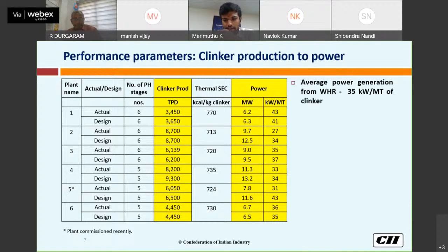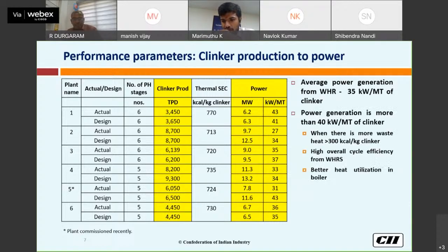Based on the table, the average power generation from WHR in India is around 35 kilowatt per metric ton of clinker, and one of the units generates more than 40 kilowatt per metric ton, where there is more waste heat, greater than 300 kilocalorie per kg. As I said, around 42% of heat we are wasting into the ambient. In this there are some avoidable losses. If the avoidable loss is greater than 300, it can generate 40 kilowatt. And if the overall efficiency of the WHR is good, that also adds value to generation, and better heat utilization in the boiler is also a factor.